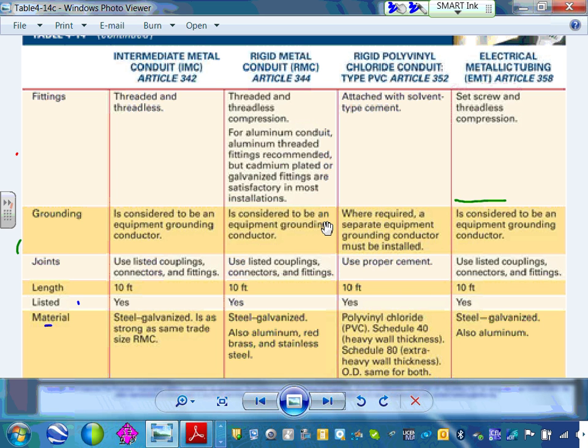Now with rigid, we can use both threaded and threadless. With PVC, they don't have threaded. You slide - have you guys done PVC? You slide the connector, and there's some cement you put on it, and you glue it basically. So glue, or the solvent cement as they call it. And for EMT, the reason why EMT is so important is because they use set screw or compression connectors, very easy to work with. Look at this one, guys, imagine doing wrenching and all this good stuff - a lot of work. So for EMT, you slide the connector with a set screw, tighten the set screw, and you're done.